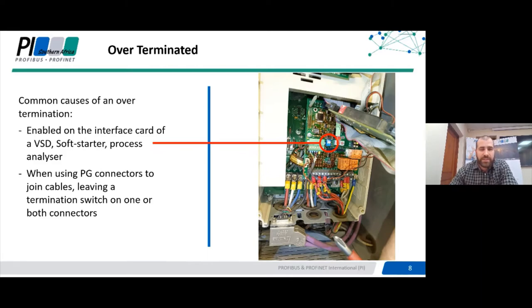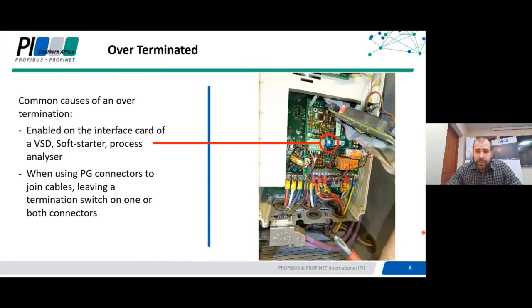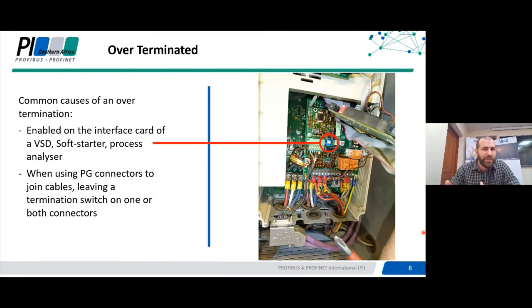By adding excess resistance into the middle of a segment, you're decreasing the signal quality — voltages will drop and this causes severe communication and connection issues within the network. So typically when you connect your high speed oscilloscope, something like Profitrace, and you notice that signal quality is below 3.5 volts or a little bit lower, a good place to start is to open up any VSDs connected within the segment and ensure that this dip switch is disabled.